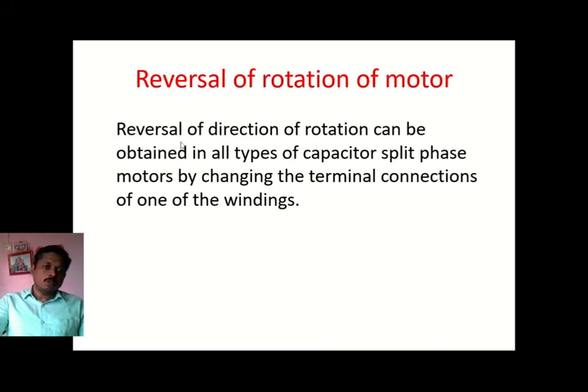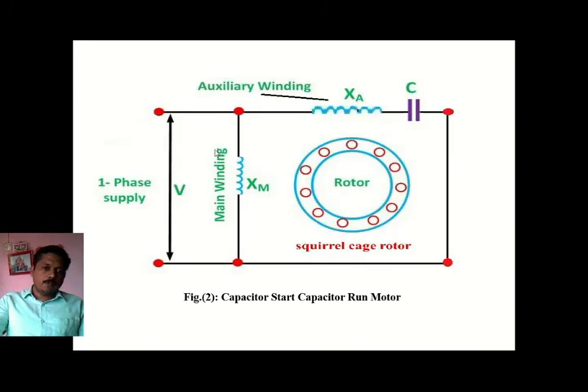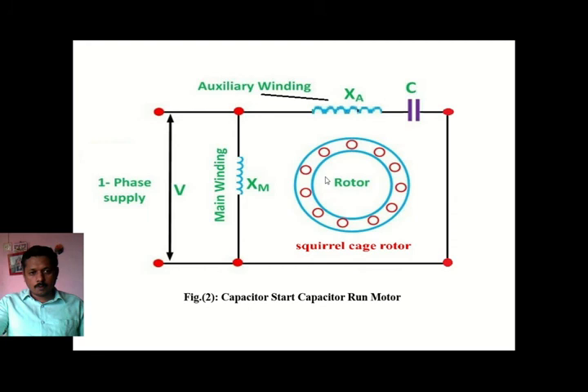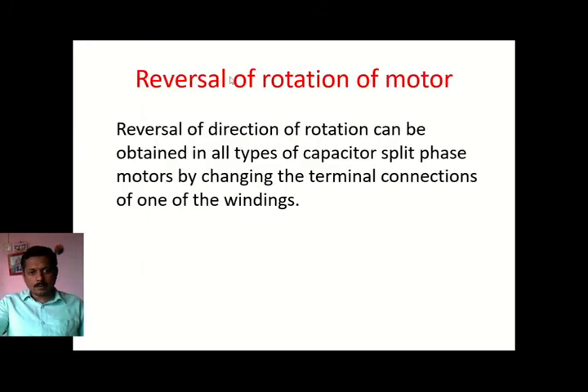Reversal of rotation of this motor can be obtained by interchanging the terminals of any one winding — either the main winding or the auxiliary winding. If we interchange the terminals of one winding, the motor will rotate in exactly the opposite direction: if it was running clockwise, after interchanging it will run anti-clockwise.